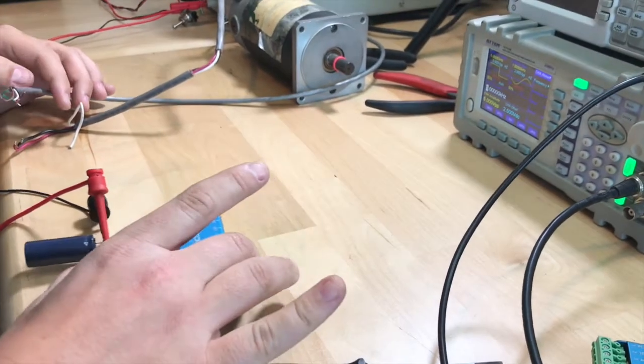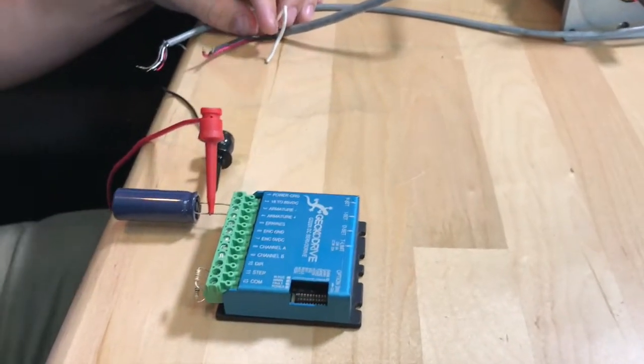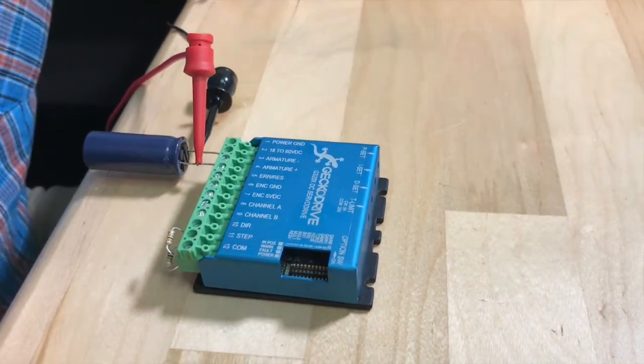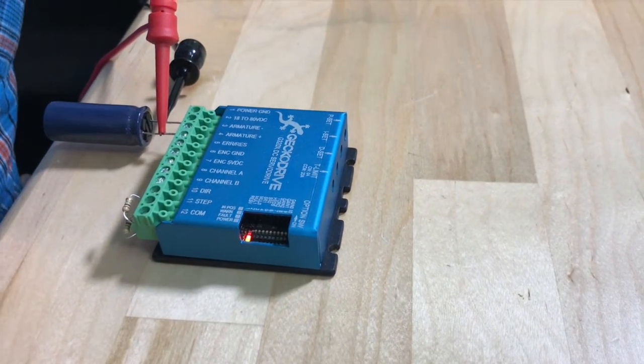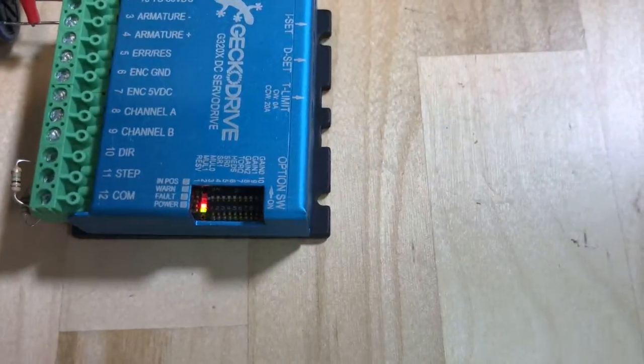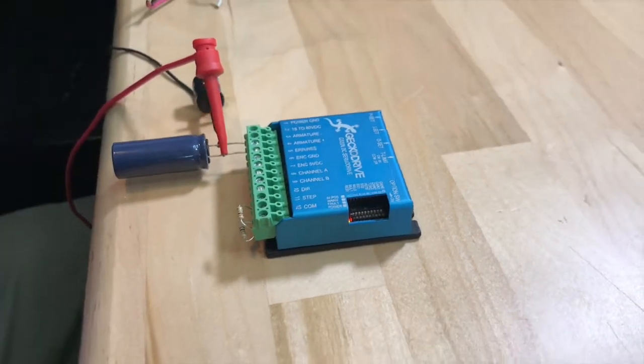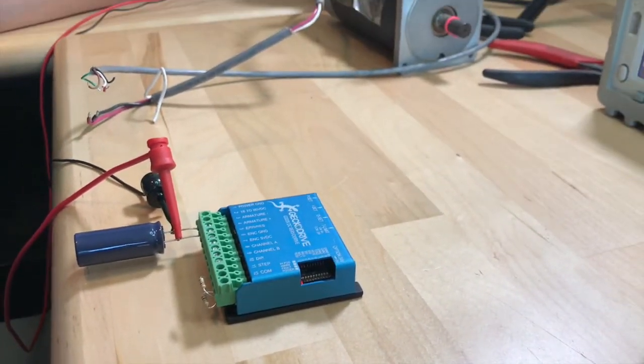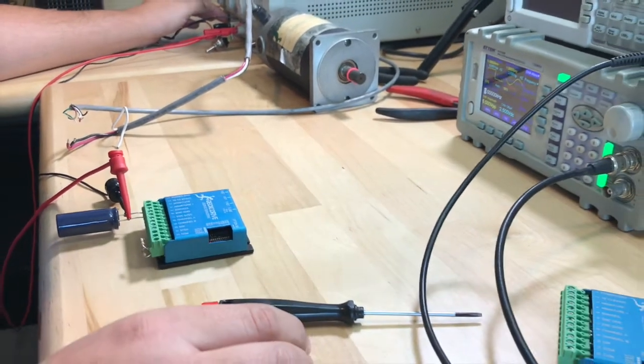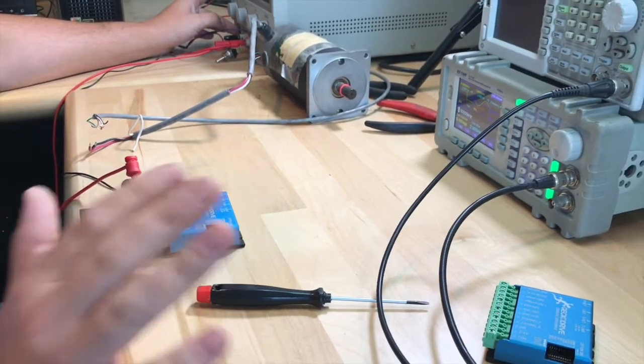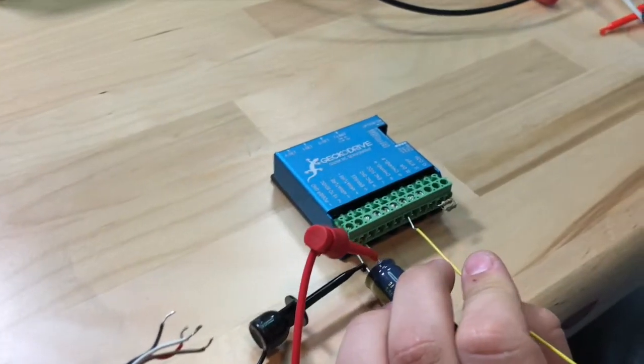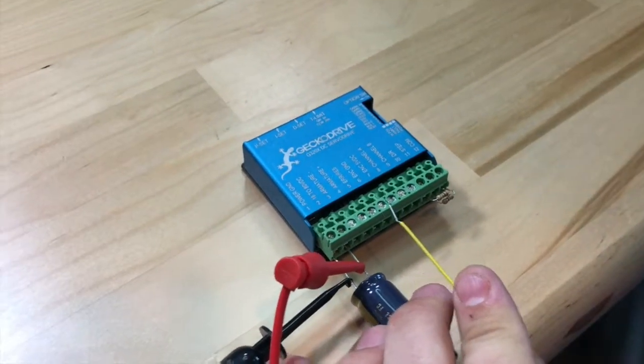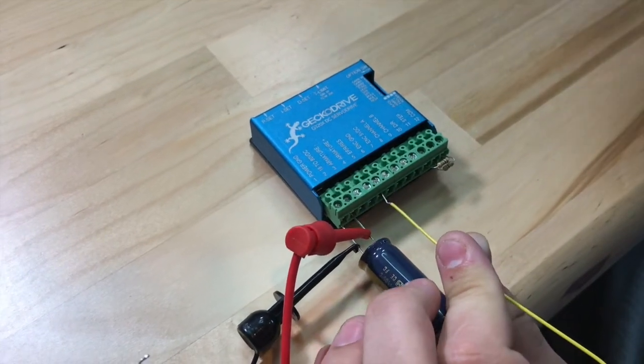So first thing we do is we turn on power and just verify that any LEDs come on. So we have red and green. That's good. When you power it on, you'll have a red and a green LED because it's powering up into fault mode. If it were to power up out of fault mode and your encoder was not there, your motor would just run away.